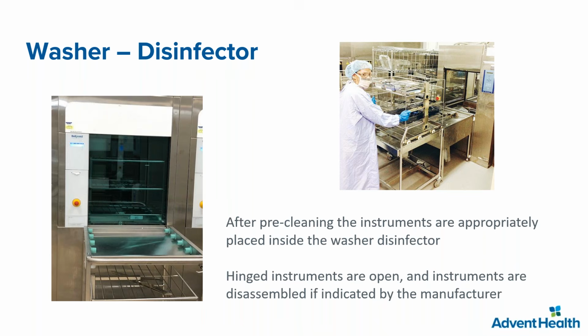And that's one of the problems: if the staff doesn't know that equipment needs to be disassembled, that equipment can have blood or any kind of fluid inside, and then it goes through the whole process of sterilization. You can then have an emergency situation in the OR when the doctor tries to use the equipment and it doesn't work, because it was not treated properly during pre-cleaning, reprocessing and sterilization. So we need to avoid that. Everything that has hinges needs to be open. Anything that has different pieces needs to be separated, cleaned and reassembled again after it goes through the washer disinfection.